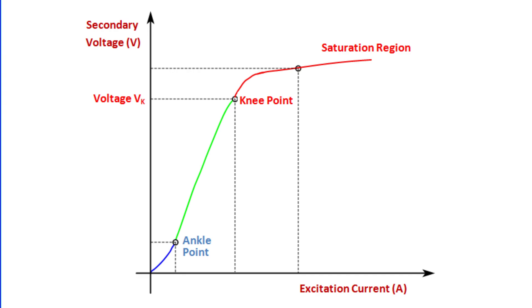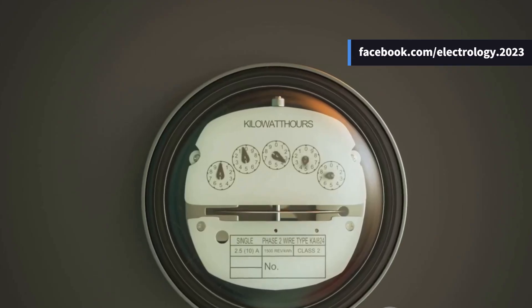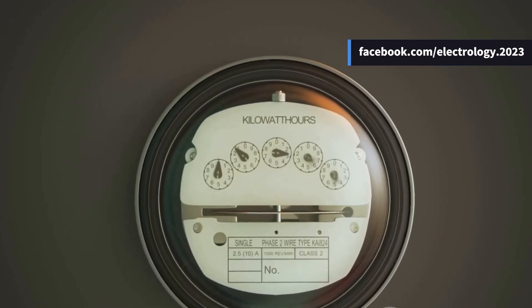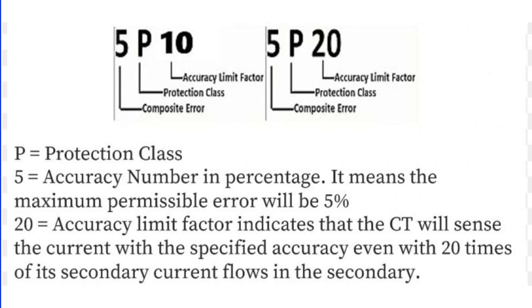But here's the issue: if a protection CT is used for metering, the accuracy under normal conditions won't meet the revenue grade standards. During a fault, the secondary current can reach 10 to 20 times the rated value, damaging the meter since meters aren't designed to handle such high currents.